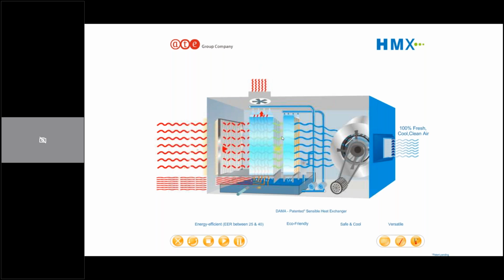Yes, understood. But normally for my application, I don't use this because I don't like to add moisture. Anything above 60-70% humidity, I feel, leads to other issues like perspiration, and condensation in certain scenarios. Some people who have asthma may breathe a little heavily. So I normally avoid anything above 60-70% humidity. Yeah, it leads to some condensation also. Absolutely. But let's say you have an open space. There is no problem, because it's a kind of a once-through system. Then you can use this.